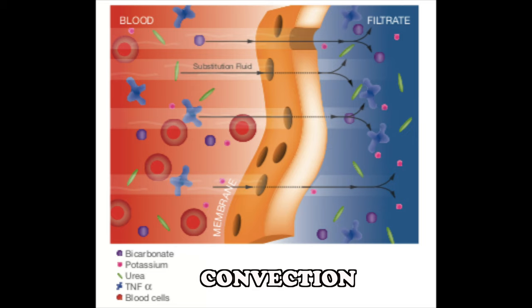Convection is the one-way movement of solutes through a semi-permeable membrane with a water flow, sometimes referred to as solvent drag. It is efficient for both larger and smaller molecules; the faster the substitution flow rate, the higher the clearance. Pressure difference between the blood and ultrafiltrate causes plasma water to be filtered across, causing solvent drag for small and large molecules across the membrane. The ultrafiltrate containing the solute should be replaced by substitution solutions, which must have near-physiological levels of electrolytes and buffer and be sterile. Convection is a hemofiltration principle.